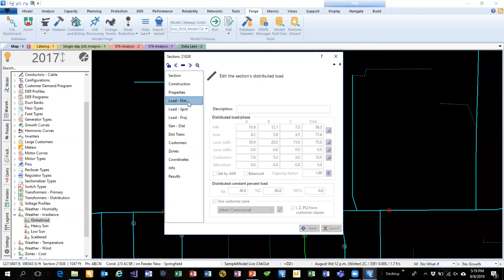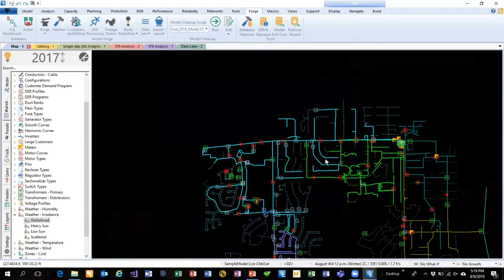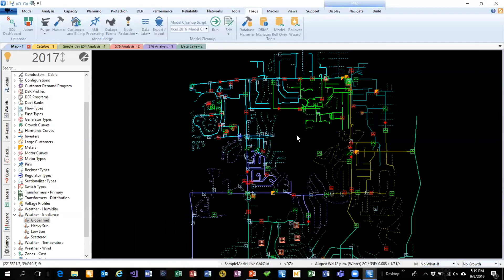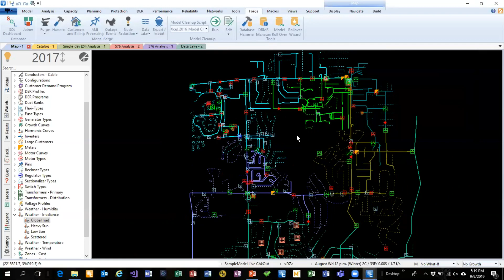The third reason is for losses. If I run an analysis with just primary included, a system like this, I'll probably get about 1% loss. If I go down to the secondary, now all of a sudden my losses will probably be 8%. It's a huge increase in losses.